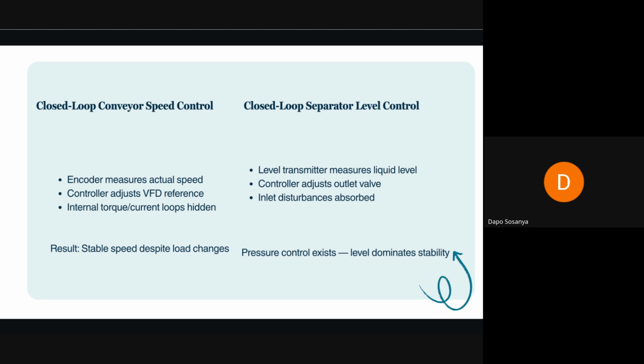And then in the separator, you have the level transmitter, which measures liquid level, and the controller adjusts the outlet valve, and the inlet disturbance will be absorbed. Let's assume that level is your main purpose. You are monitoring the level because you don't want that tank to overfill. You monitor the level, and the controller will adjust the valve based on the level and your set point, so that the level in the tank will be kept constant.